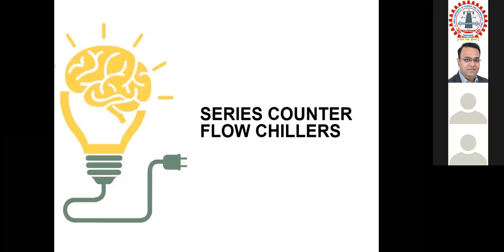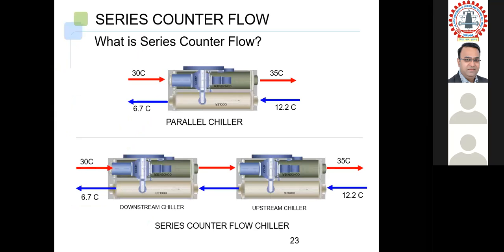And then the third technique which we have used is called series counterflow chillers, which a few of you might know as cascading chillers. But this is what is series counterflow. So in a chiller plant, you have multiple chillers in parallel, one after the other. At one side, they receive the chilled water from the air handling units, which is inside the building, cooling the air.